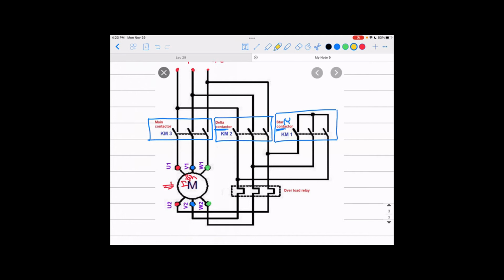So bear with me. For this delta contactor, look at what happens if this closes. It's taken from here, that is phase A, if you remember, of the motor. That's taken from phase A, going here, down like that, back here, connected to the second one, which is phase B. And the second one is taken from here, that is phase B of the motor. And if you follow it down here, you're gonna connect it here to phase C. And back here, from the motor again, that is phase C of the motor. If you follow it down there, it's connecting it to the end of the first phase. It's how you connect as delta, if you remember. You're just connecting the ending of one phase to the beginning of the next phase. That's how you can connect as delta.